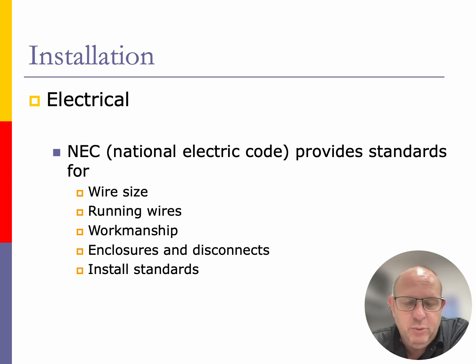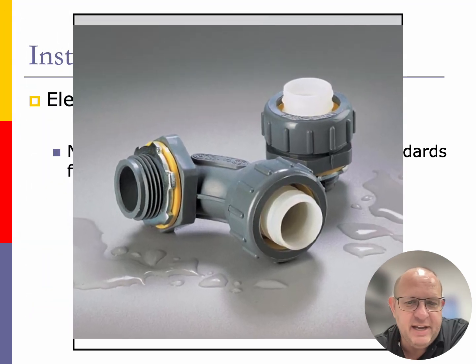Now, what I'm showing you here is a picture of a liquid tight connector. These are the conduits that we're going to be running on the outside of the unit. They provide protection from the weather, UV protection, and also wet weather applications, which we'll get into later on. But these are liquid tight connectors, and they're specifically made to attach outside to that whip and disconnect as we're running it from the disconnect to the outdoor unit itself.